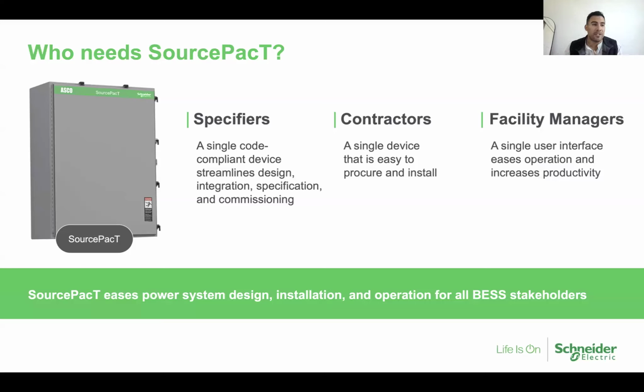So if you're installing a PV or have thoughts of adding on an energy storage system to your facility and don't want to retrofit existing breakers or add a complicated PLC, our SourcePacT interconnection product can be installed downstream of a spare breaker to add on that PV or energy storage system to your facility with ease.